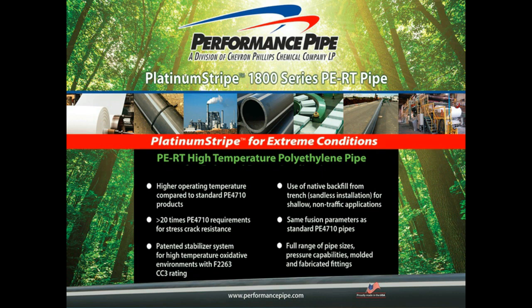And here's a common question I get on the 1800 series PERT, dealing with the thermal expansion and contraction of PERT materials at elevated temperatures. It's wanting to know if the same rule of thumb of 1 inch per 10 degrees Fahrenheit per 100 feet of pipe applies. And the answer is yes. The coefficient of thermal expansion for the PERT materials is very similar to the standard PE4710 materials. So the same rules and guidelines apply when dealing with thermal expansion of PERT as traditional PE4710.